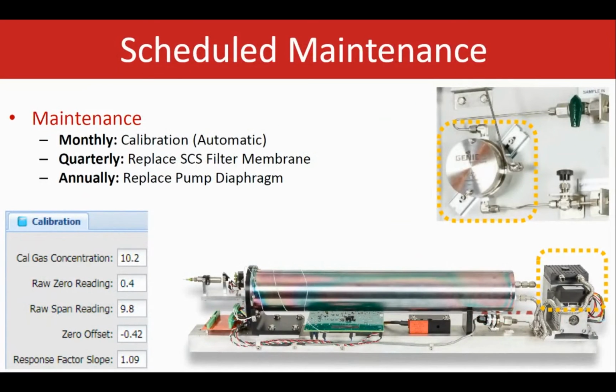On the maintenance side, that is very important. AccuLase is a very, very low maintenance analyzer. It does not require any consumables. We recommend monthly automated calibrations. The only maintenance for this unit is basically replacing the membrane filters on a quarterly basis, if required, if there is any leak, and the vacuum pump diaphragm annually, and that's it. Very low cost for the maintenance, very easy. Therefore, it's a huge advantage in a long-term investment in this unit.